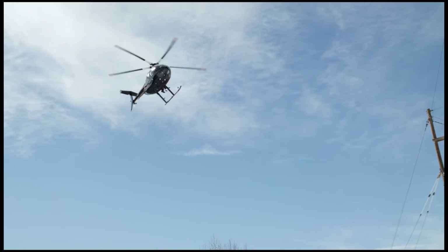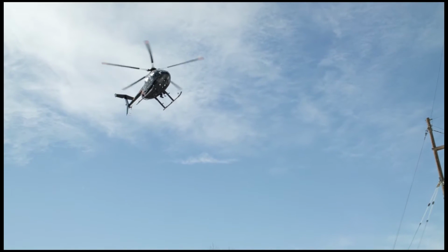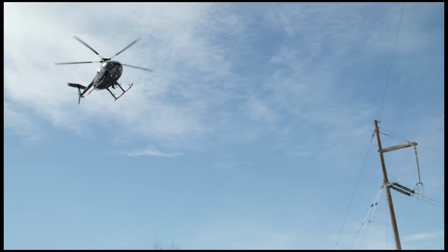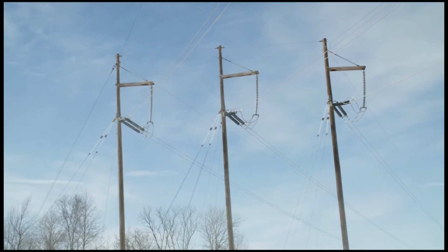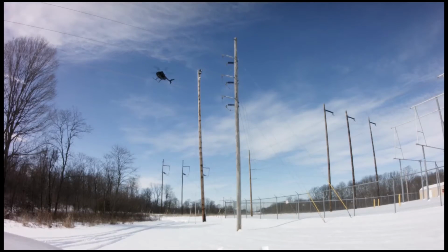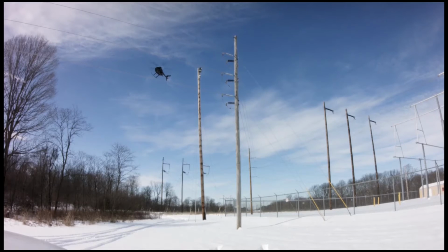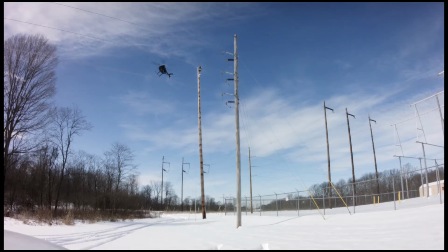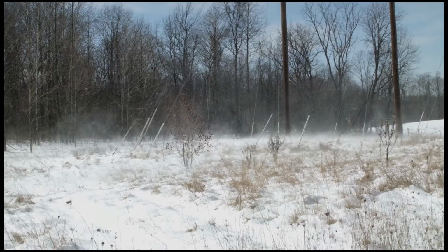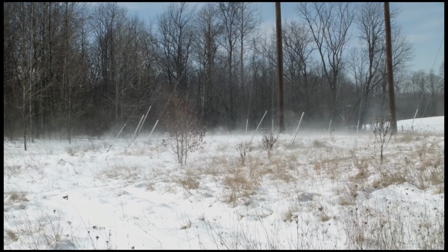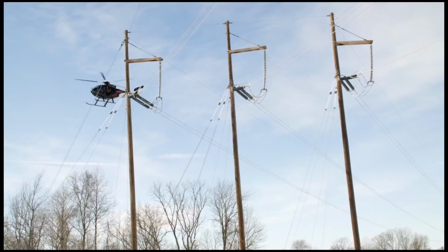By using an aerial provider and working through a helicopter from a platform, the lineman was able to aerially access the line, connect himself with the line, and become energized at that 345 kV level. We were able to reduce that repair time to about 4 hours.